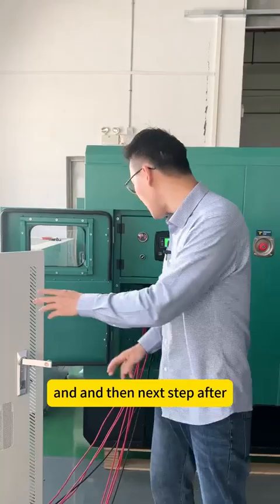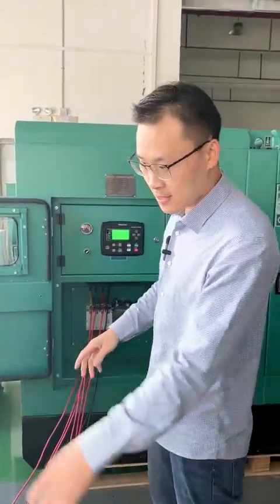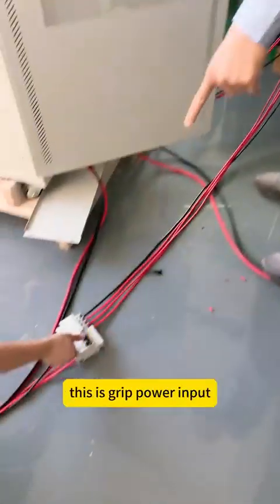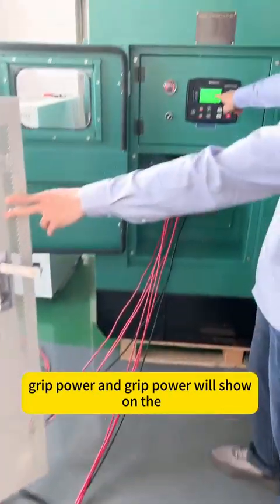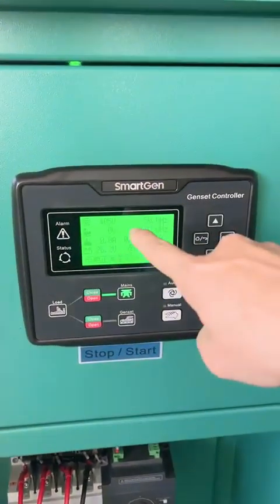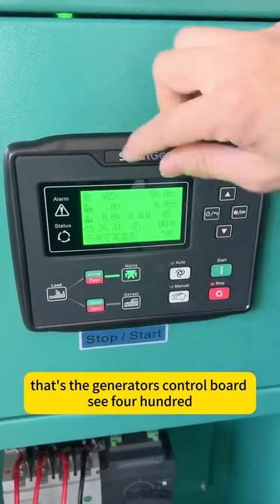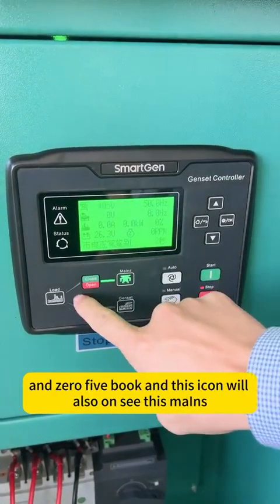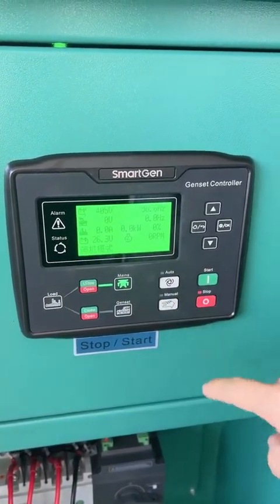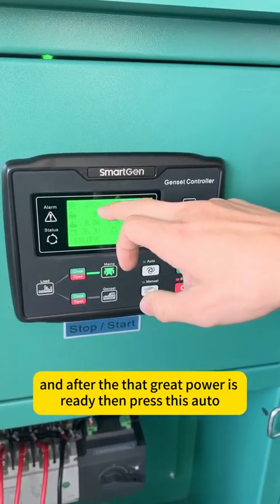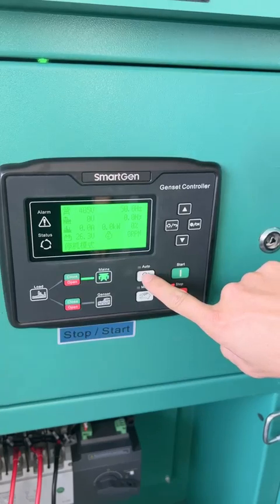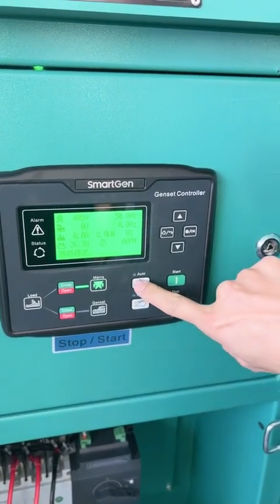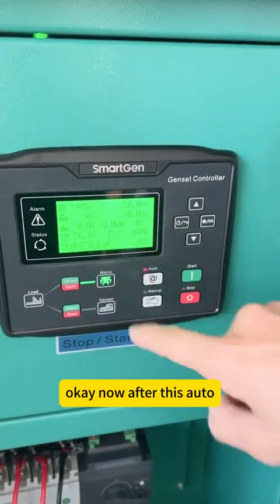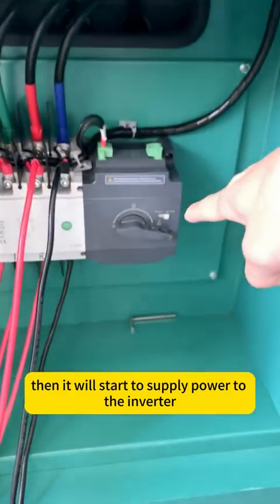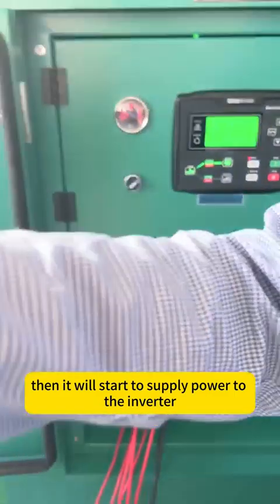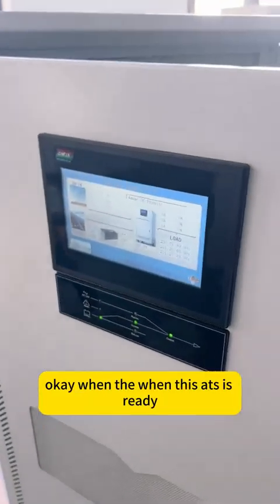And then the next step, after you do all this connection with the diesel generator, we turn on the grid power. This is the grid power input. And grid power will show on the diesel generator's control board, see? 405 volts. And this icon will also turn on. After the grid power is ready, then press this auto. Now after this auto, it will start to supply power to the inverter.